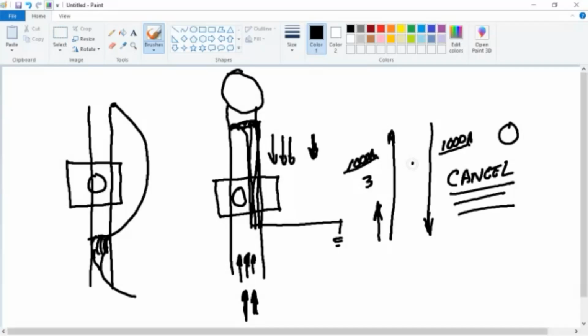But have I done anything with the inside inner core of the cable? What direction is it going? Only one. So will the fault indicator work? Yes. It will. If my neutral conductor is going in and back out, and I have the fault indicator over both of them, right here in this area, it will read nothing off the neutral. It canceled itself, but it still will read the measurement of the core conductor inside, okay? That magnetic field will still be emitted and captured by the fault indicator. So that is a legal installation.